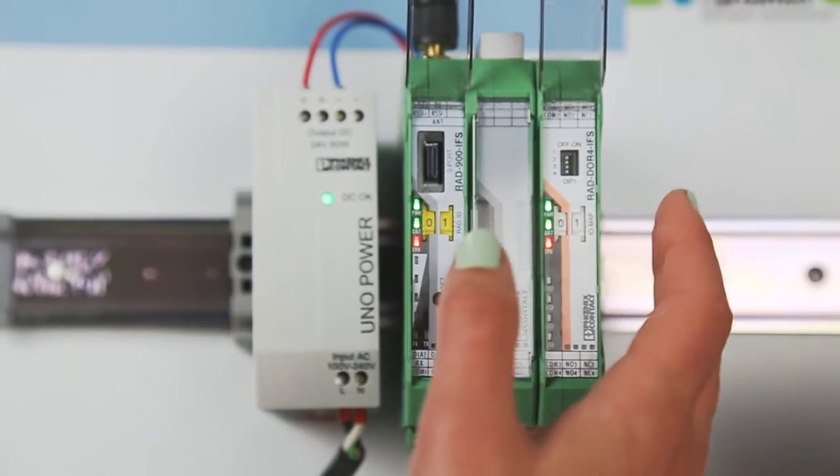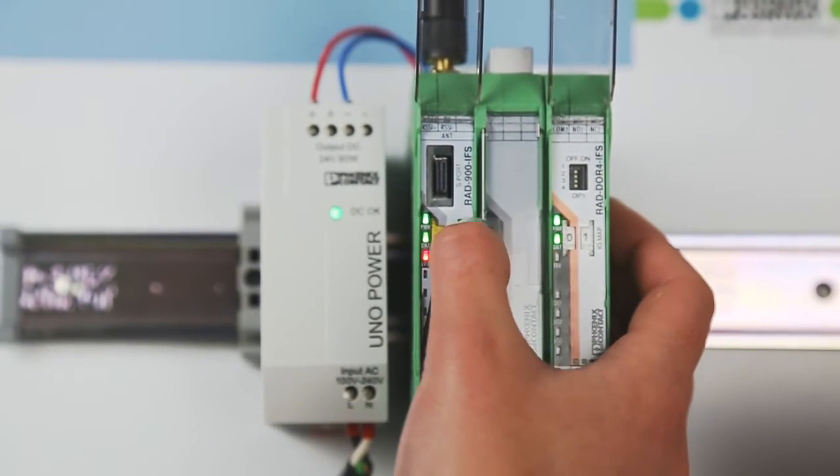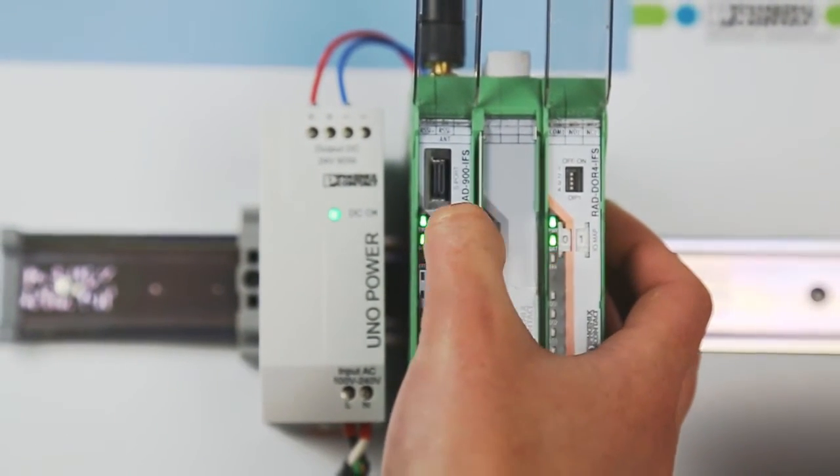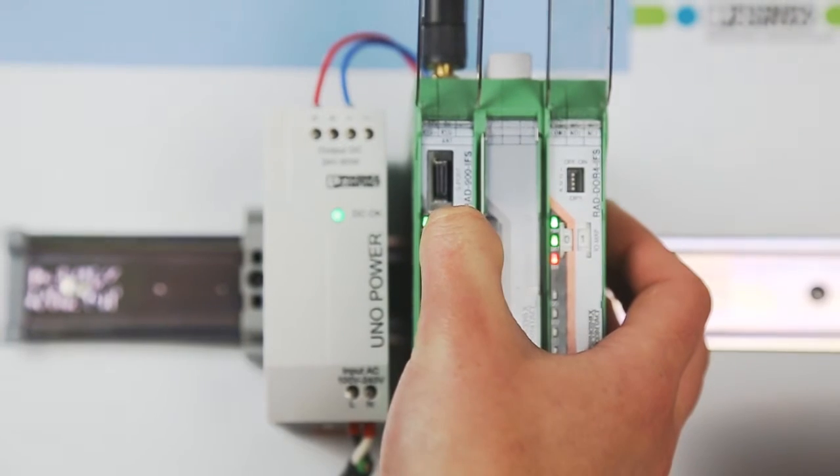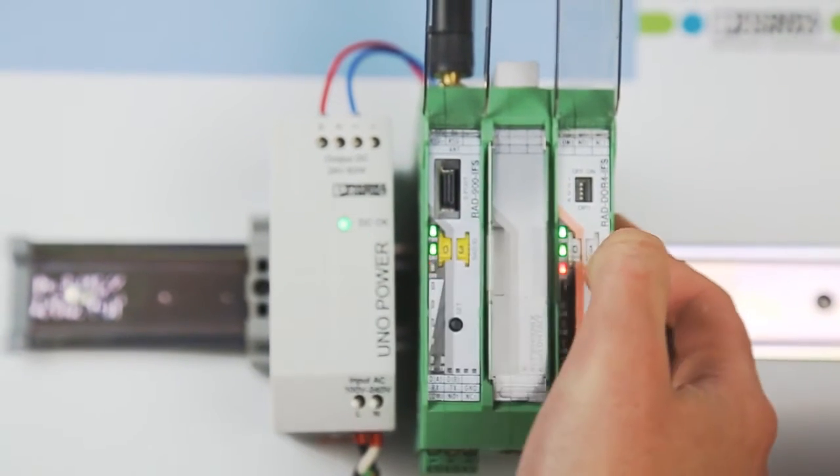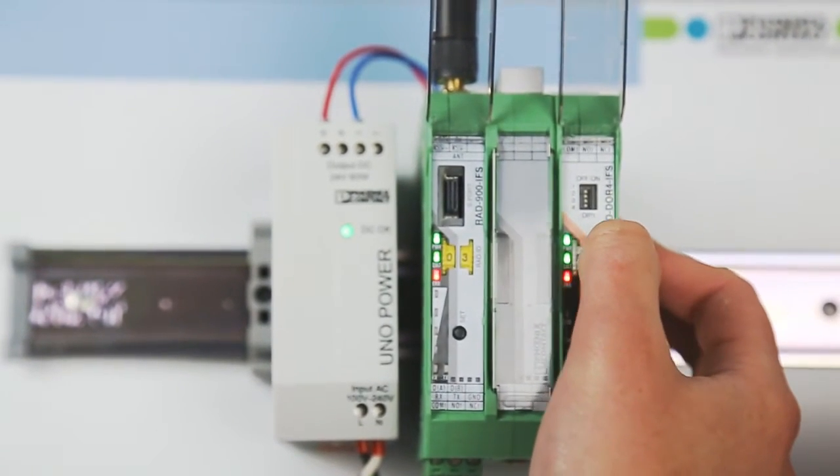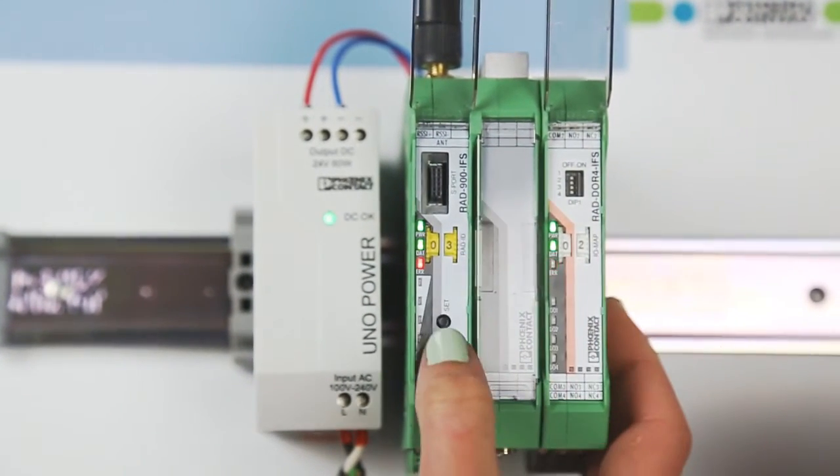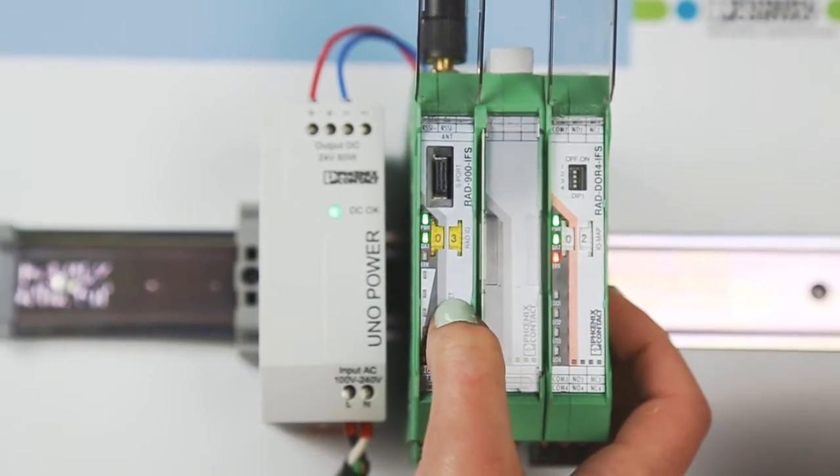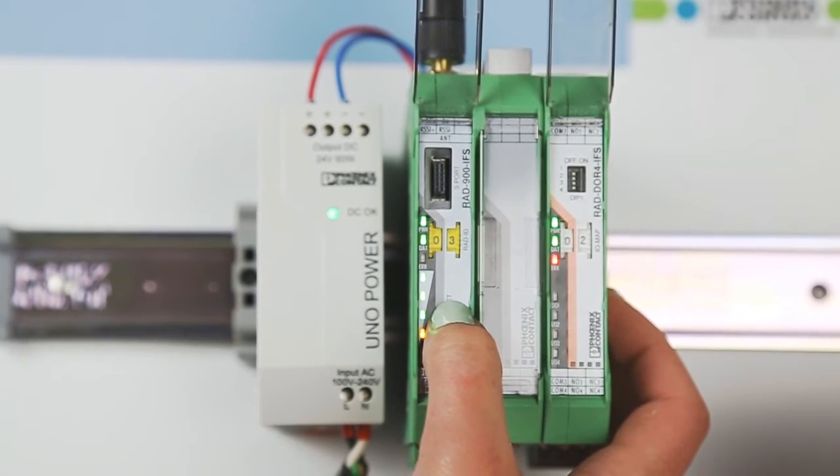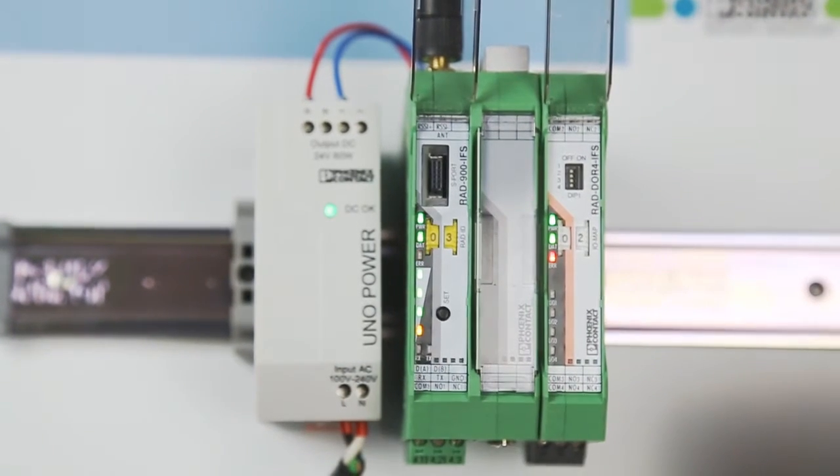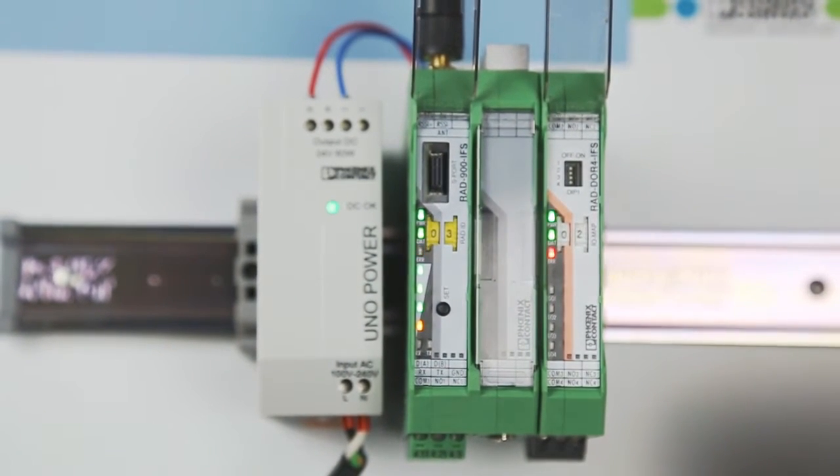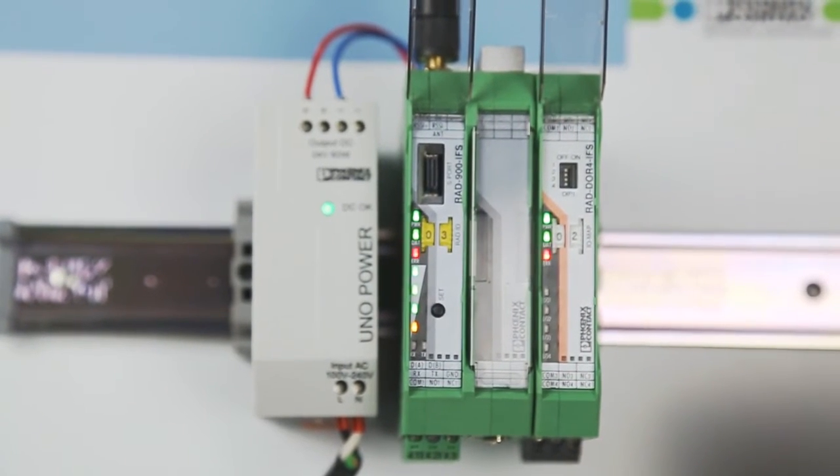Lastly, configure the third wireless module to a repeater slave by setting the yellow thumb wheel to 03. Address the I.O. module attached to the wireless module by setting the white thumb wheel to 02. Press the set button for one second to read in the thumb wheel settings.